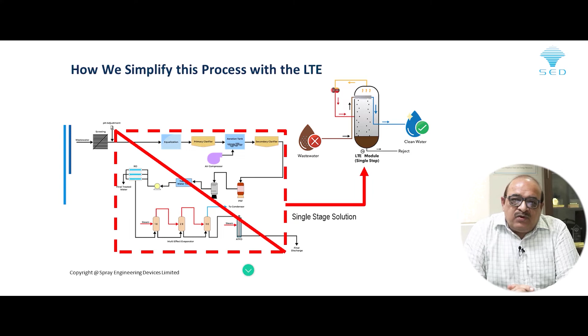With LTE, there is a game change. Now, when we use LTE, you don't require a boiler, you don't require a turbine. Of course, you require power. Now, there is no heat input in this particular system, and the vapors which are generated, we are using MVR to recompress those vapors and use them as a heat source in our system. Now, this MVR acts as a boiler for this low temperature evaporation technology. When we use this, we recover heat from the condensate, and we don't require any cooling tower for heat rejection. So with this, the steam and cooling tower requirements become zero.